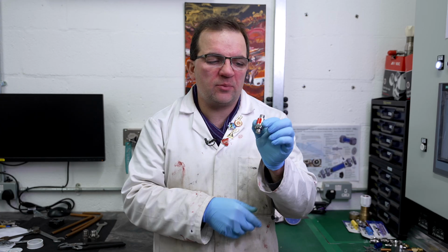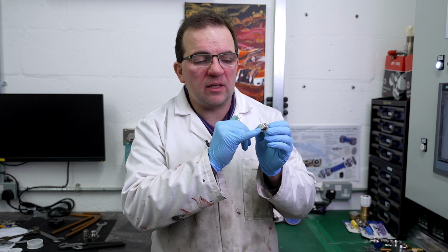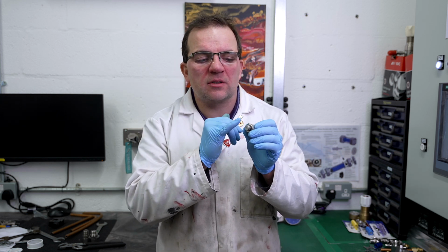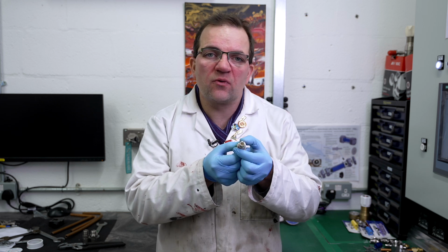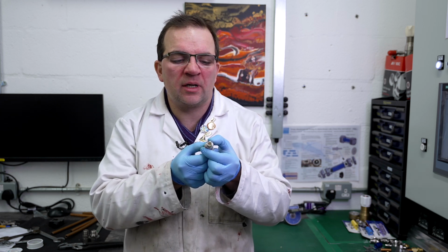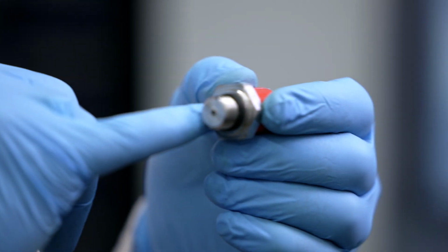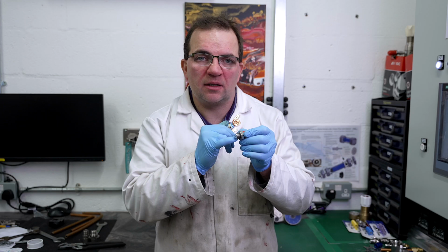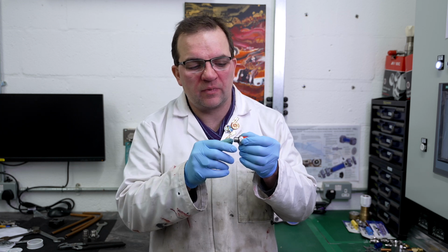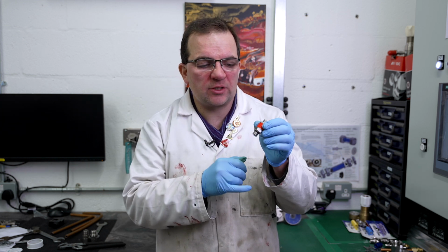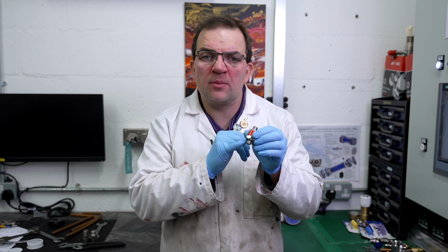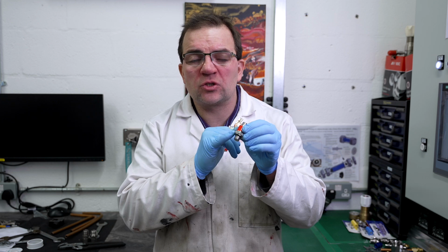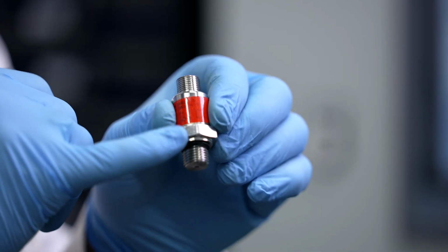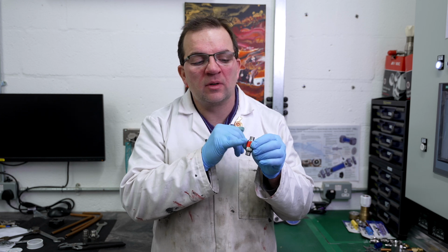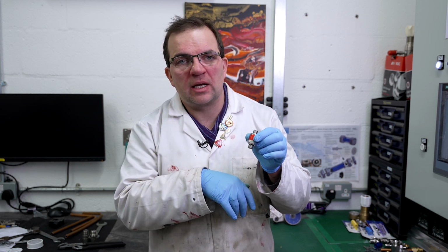An alternative to the manual pressure gauge is a pressure transducer, where you will have an inlet for the pressure to be fed into. This is the working side, and then you'll have some form of electrical connection on the other side as well. Most pressure transducers will also require some form of sealing to go into the threaded system. With a digital pressure transducer, there is also a diaphragm in here, but on the other side there is a strain gauge inside the pressure transducer that, when deformed, will give an output signal which the pressure transducer reads and gives you your pressure.